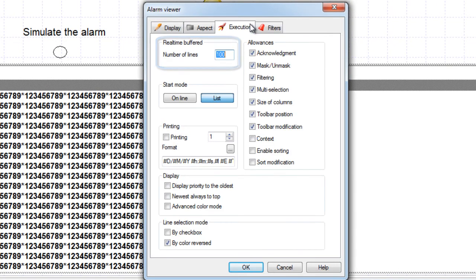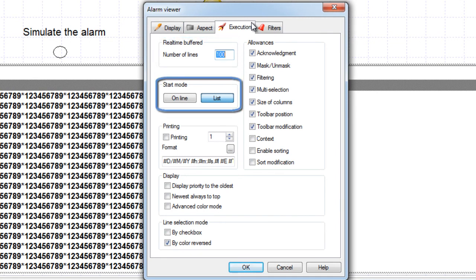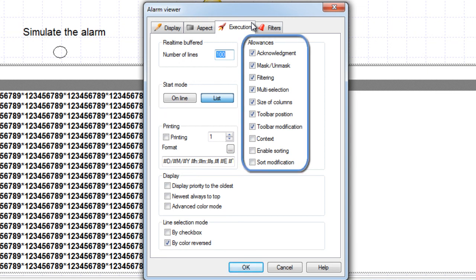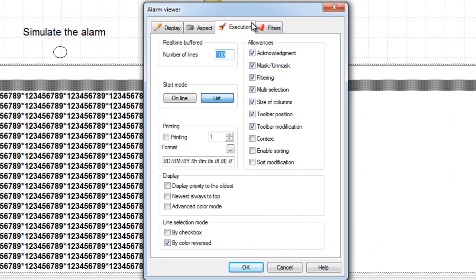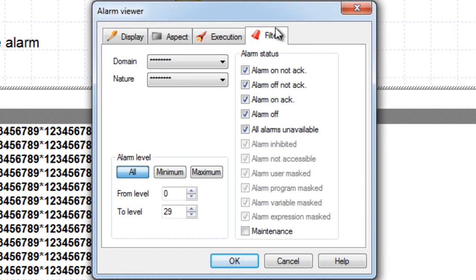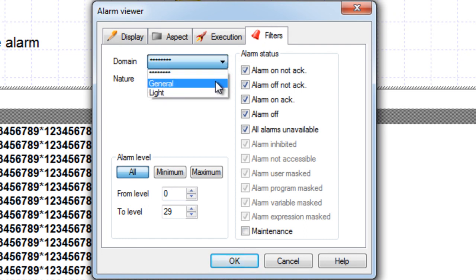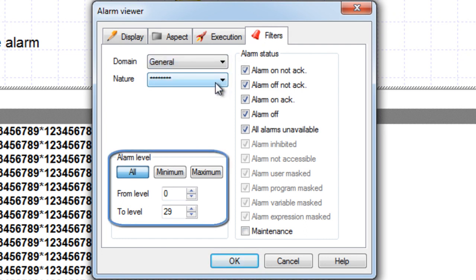From the Execution tab, you can select the number of lines you want to manage. You can select the mode — list or online — as default. You can also select the allowances or authorizations that the operators are permitted at runtime. Here we'll authorize the operator to print the selected alarm by clicking the print icon in the toolbar. The filter tab allows you to filter the alarms you want displayed — for example, alarms with domain 'general'. You can also filter the alarm priorities.